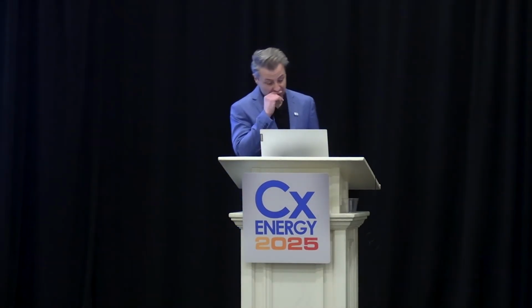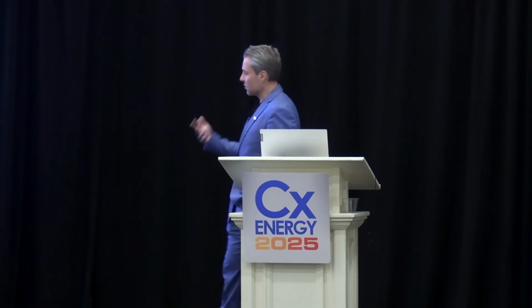Air and water side economizer, that's a much more intensive process. Most of us probably know what air side economizer is, where you use cooler air for cooling. Water side's a little bit more complicated, where you have to have cooling towers and heat exchangers and some more infrastructure, but maybe that's feasible as well. And with the upcoming wave of immersion cooling for servers, where they are sitting in a dielectric liquid, and that's providing the cooling, and that's just being pumped back through a heat exchanger, and your chilled water's on the other side of that heat exchanger, you might need to have some chilled water and economizer cooling as part of a future upgrade.